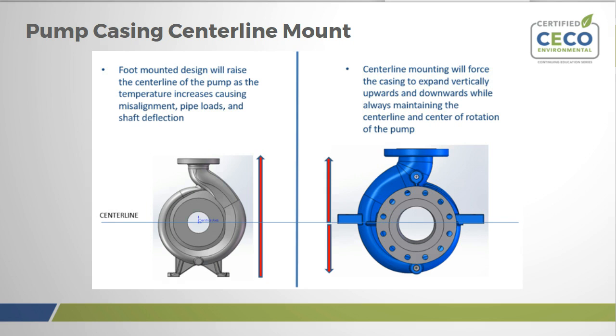So in the case of this pump, it's sitting on a base plate. It's sitting on a foundation of some sort. As this pump increases in temperature, the pump on the left, as it increases in temperature, the height of that flange is going to move upwards. Also, the center line will move up along with it. We're trying to keep the shaft and the impeller spinning in the center of that pump. If the center line of the casing is changing, then I'm either bending the shaft or I am at risk of contacting the rotating area with the stationary portion of the pump.